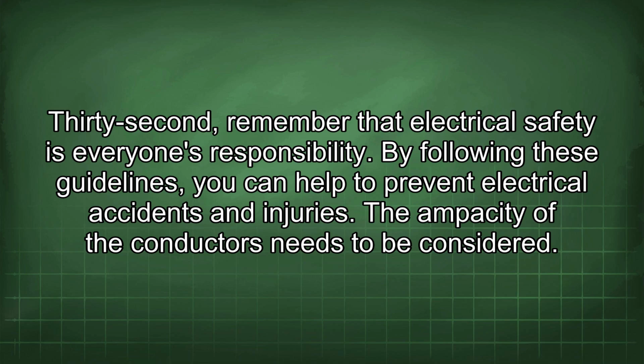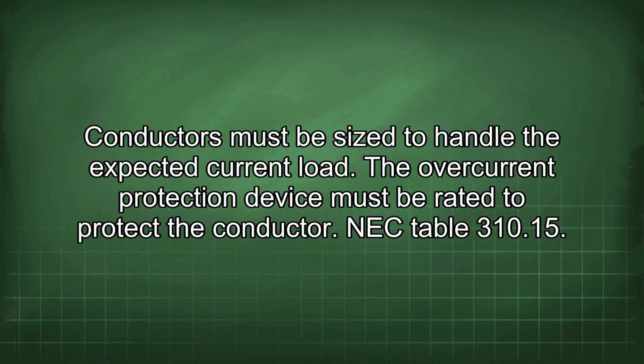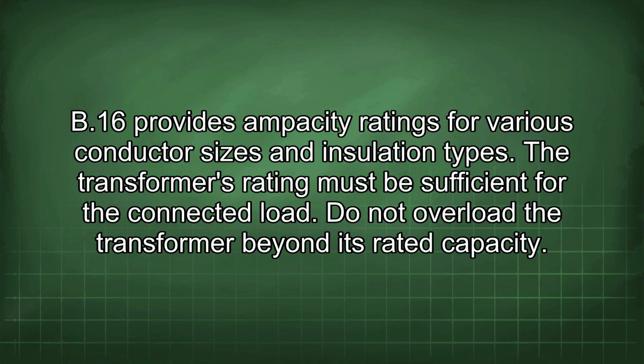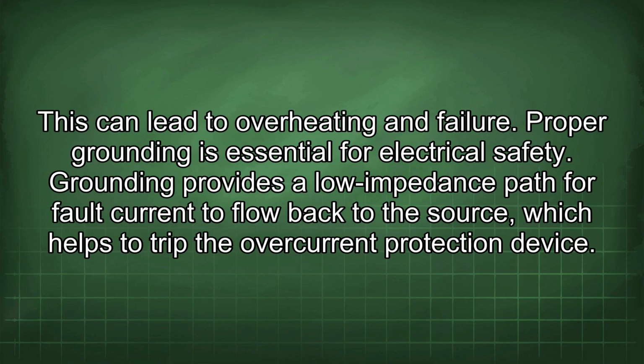The ampacity of the conductors needs to be considered. Conductors must be sized to handle the expected current load. The overcurrent protection device must be rated to protect the conductor. NEC Table 310.15(B)(16) provides ampacity ratings for various conductor sizes and insulation types. The transformer's rating must be sufficient for the connected load. Do not overload the transformer beyond its rated capacity. This can lead to overheating and failure.